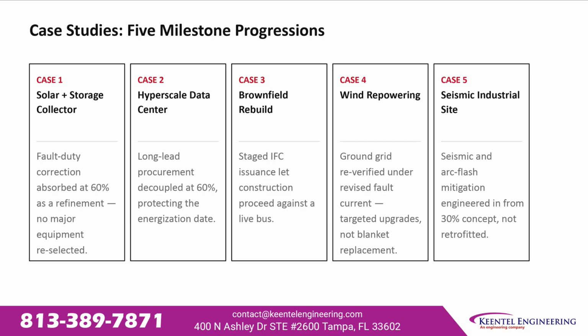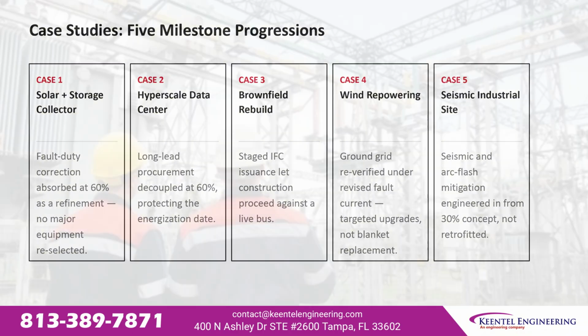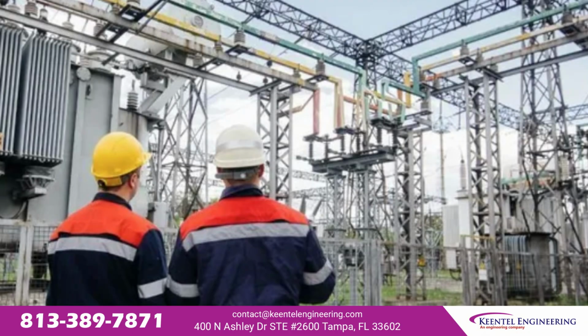The fifth is a seismic industrial site. Seismic qualification under IEEE 693 and arc flash mitigation were incorporated at the 30% concept stage, shaping equipment selection and layout from the start instead of being retrofitted into a design that had not accounted for them.